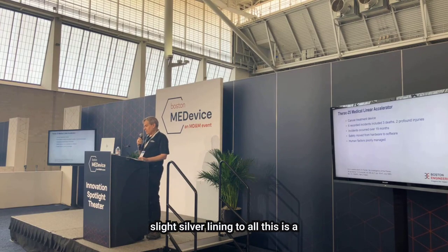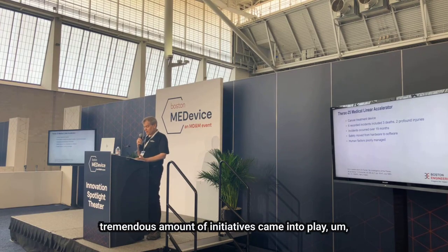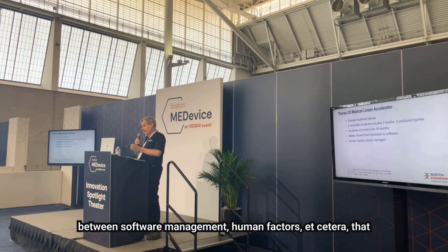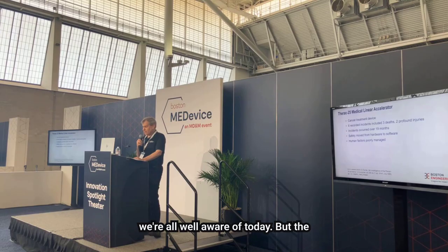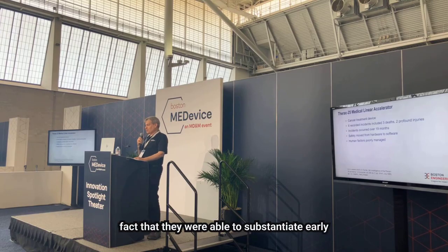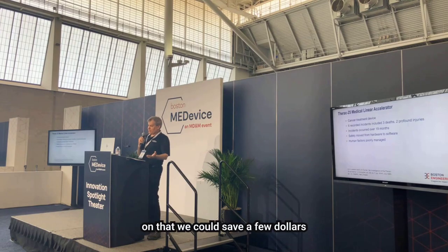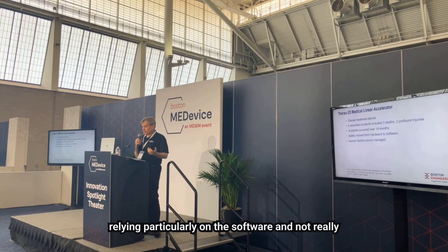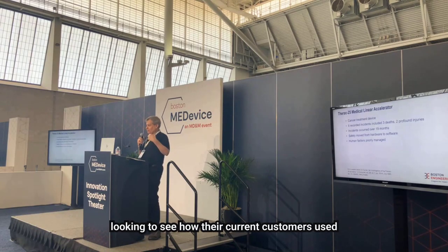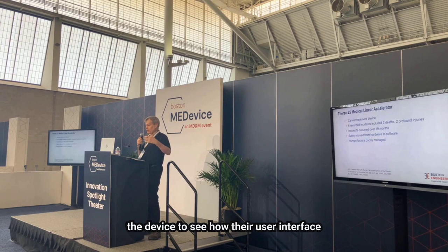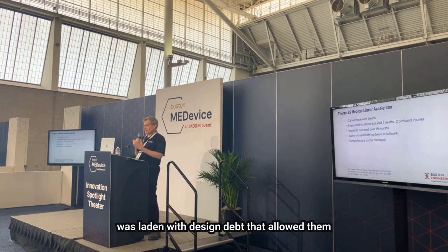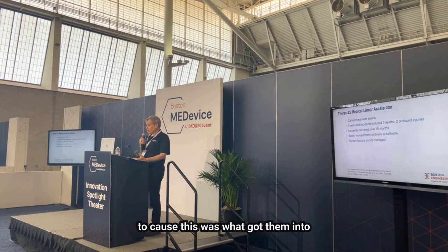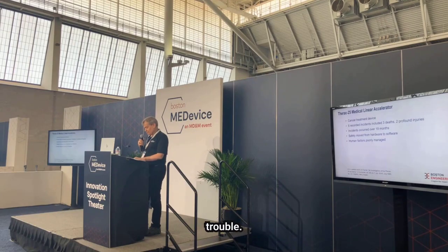The slight silver lining to all this is a tremendous amount of initiatives came into play between software management, human factors, et cetera, that we're all well aware of today. But the fact that they were able to substantiate early on that we could save a few dollars by taking these hardware safety systems out and relying particularly on the software, and not really looking to see how their current customers use the device, to see how their user interface was laden with design debt that allowed them to cause this, was what got them into trouble.